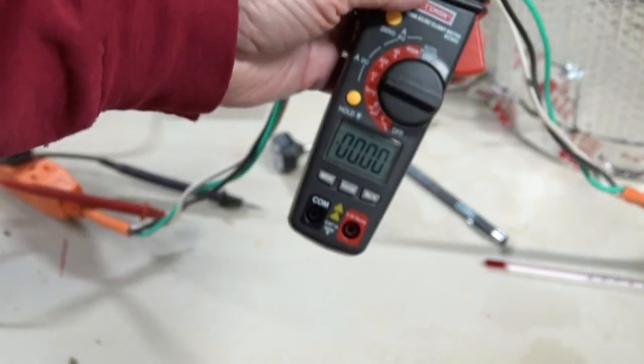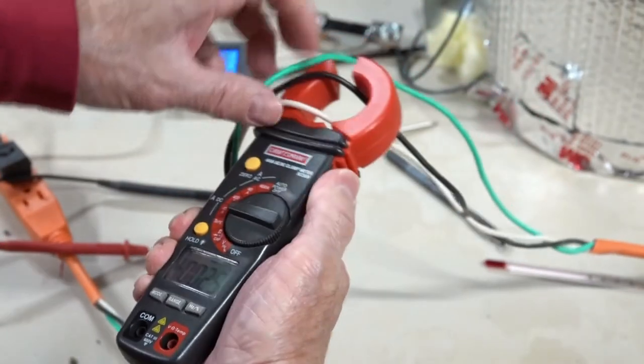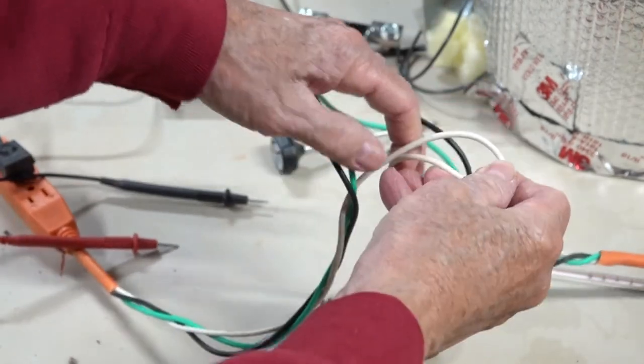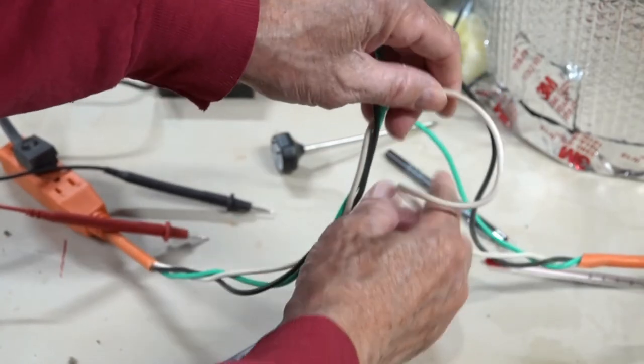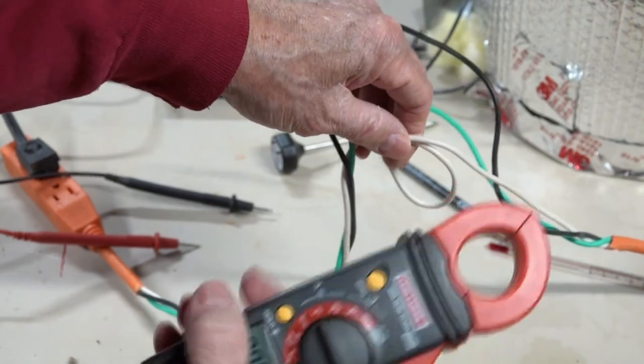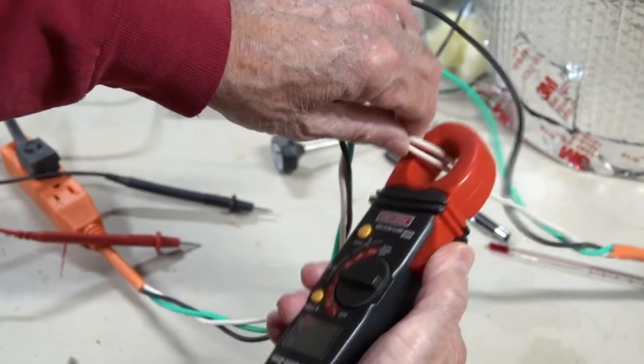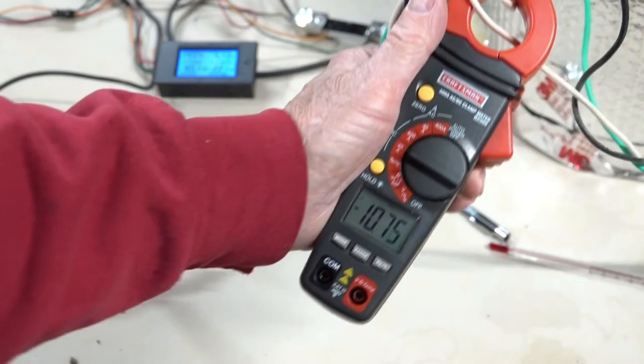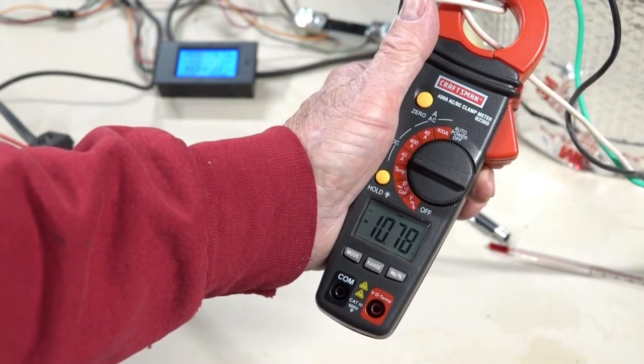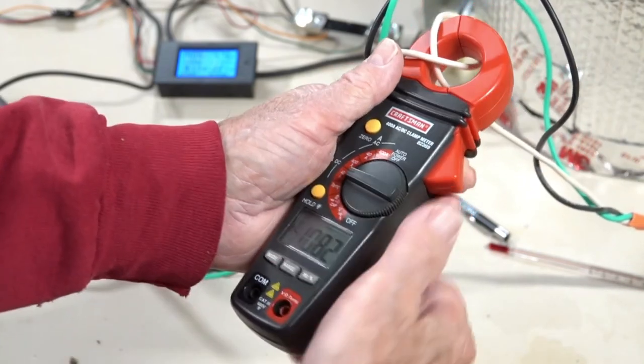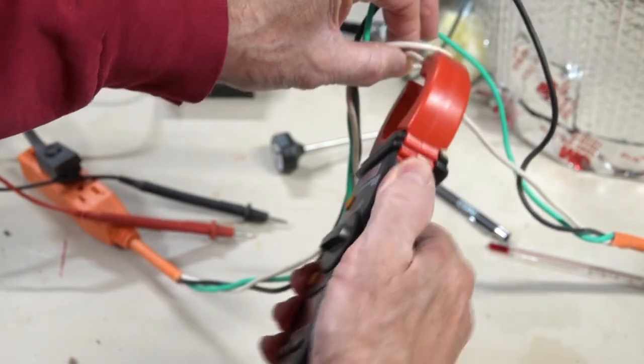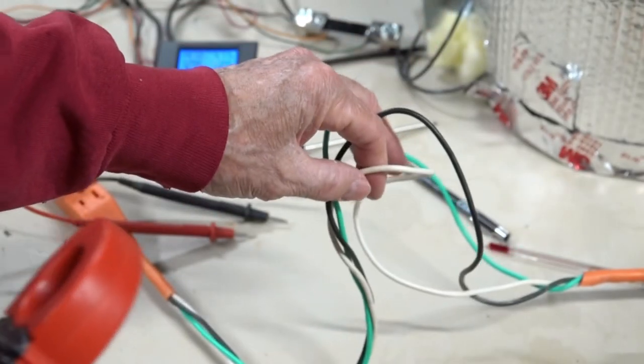So, let's try another little thing that's a little bit different. Doesn't matter which lead we use here, because you get the same measurement in both of them. Let's loop it around like that. See that? Doubles it. 10.74, 10.73, 10.76. That is because it thinks there's two current carrying leads in there.